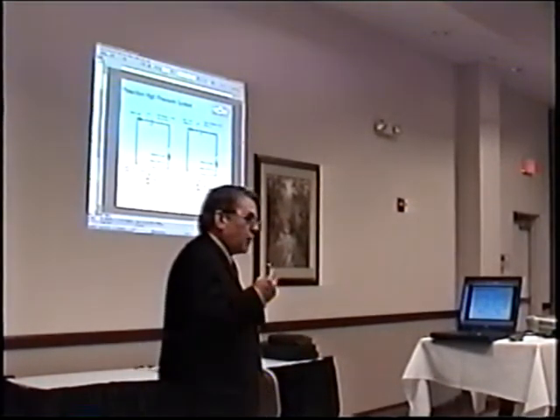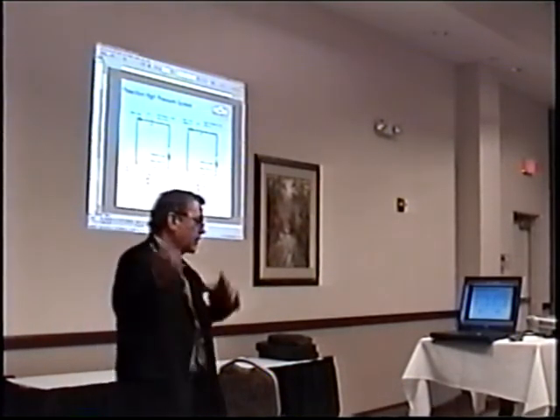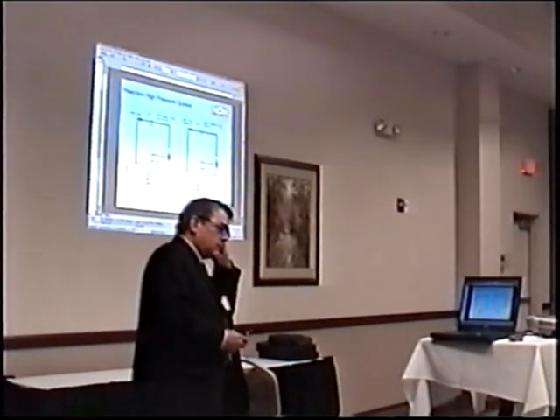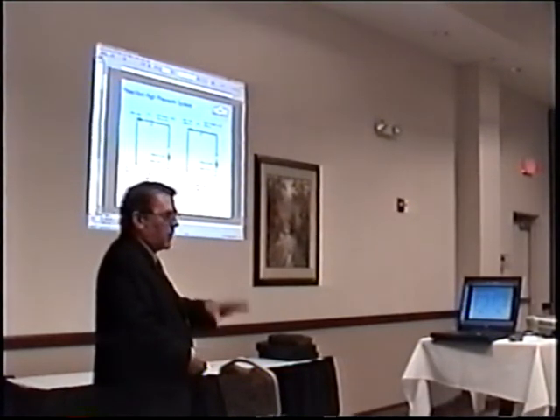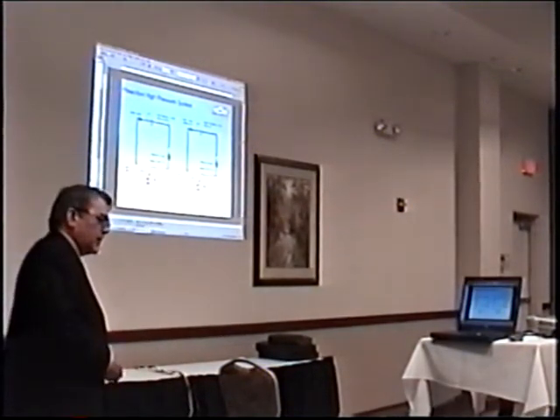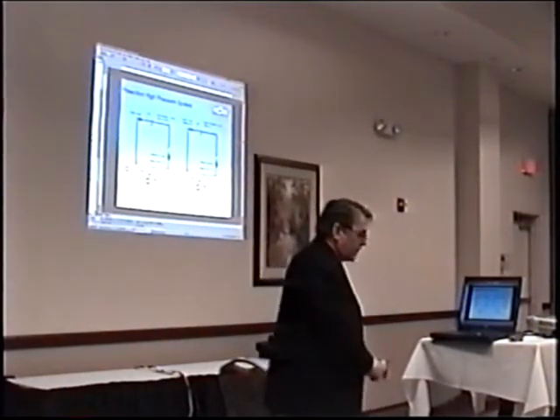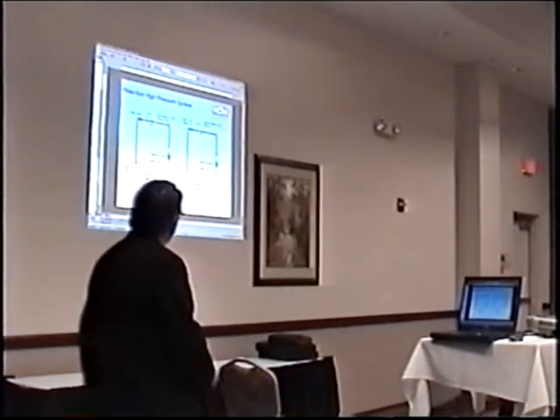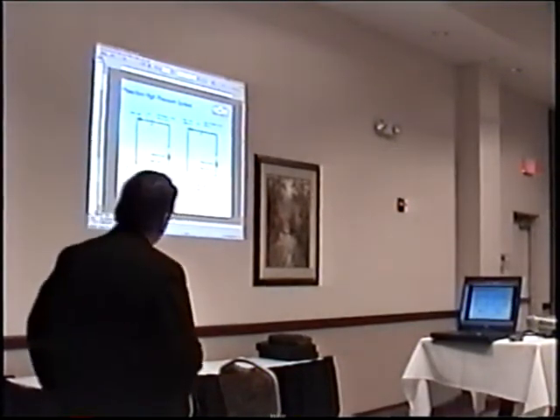Well, Marioff's primary ship pump unit has what they call a break tank on it. Water comes into a tank, and then it comes out of this tank into each of the pumps, which is great. It's a nice, convenient way to do it. But because of the experience in Alaska, I was worried about this water sitting in the tank, possibly getting algae growth in it, and there's no filtration afterwards. I noticed at least, I think it's Chemetron, they have a tank, and they have a strainer on the outlet of the tank. It's a very smart thing to do. If you get a higher pressure system, you can't put strainers and pull them apart. Those things go wrong. You can't put filters either.